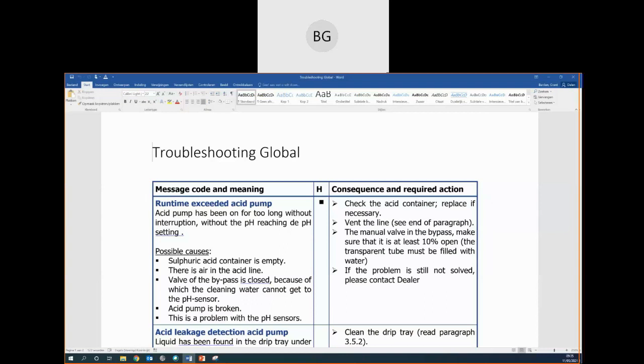Check the acid container, replace if necessary. Vent the line. For venting the acid system, see the chemical dosing handbook. The manual valve in the bypass, make sure that it's at least 10% open, and the transparent tube must be filled with water. This is to say that you have sufficient water over the pH sensors. If the problem is still not solved, please contact the dealer. That will be yourselves. And if you can't solve the problem, then contact me.